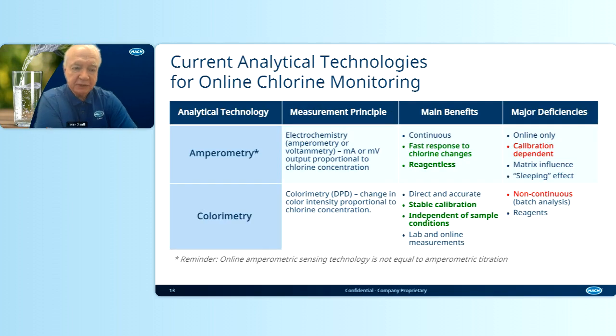So, analytical technologies. With amperometric, we're looking at millivolts, milliamps, output proportional to the chlorine concentration. They are continuous. You get a fast response to chlorine changes, and it's reagentless. Major deficiency, it's online only. It's calibration dependent. Matrix influences, we can go into a little bit later, and then it also has a sleeping effect. With colorimetry, we're measuring a change in color intensity proportional to the chlorine concentration. It's direct and accurate, with stable calibration, independent of sample conditions. You've got lab and online with the same method, but it is non-continuous and it does require reagents.